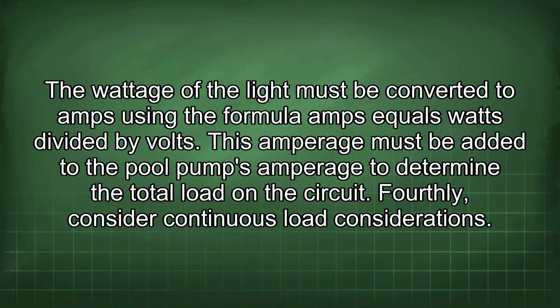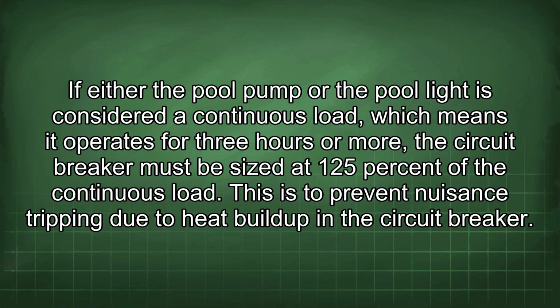Fourthly, consider continuous load considerations. If either the pool pump or the pool light is considered a continuous load, which means it operates for 3 hours or more, the circuit breaker must be sized at 125% of the continuous load. This is to prevent nuisance tripping due to heat buildup in the circuit breaker.